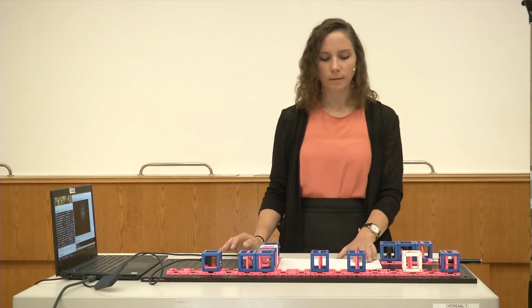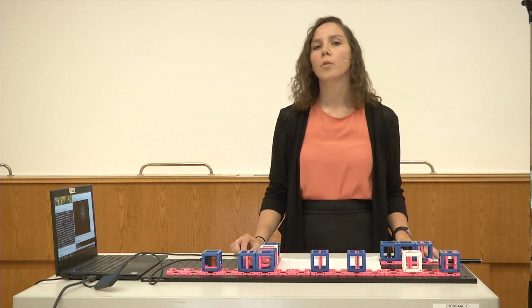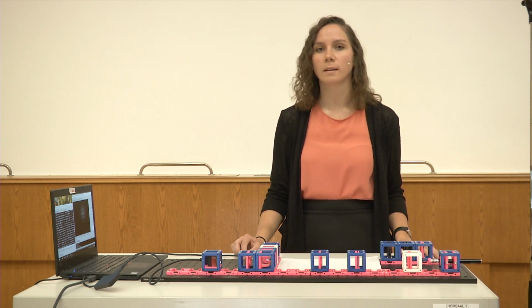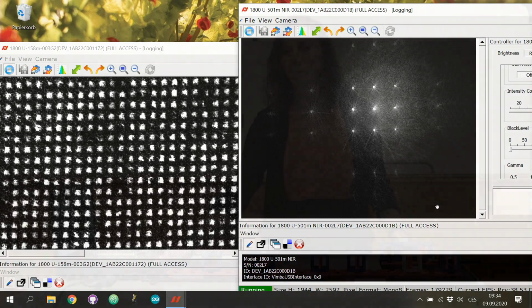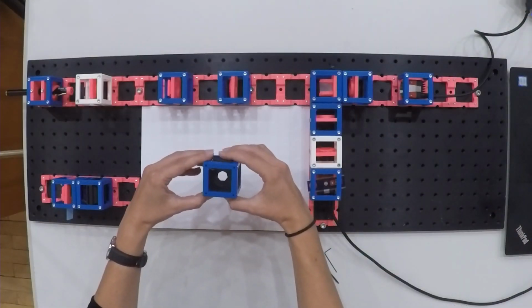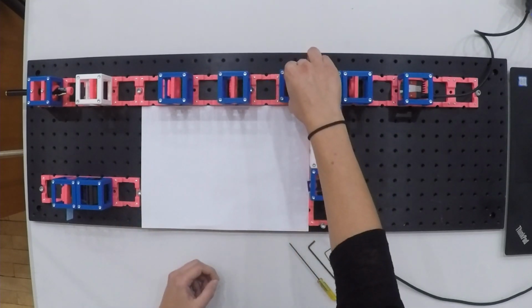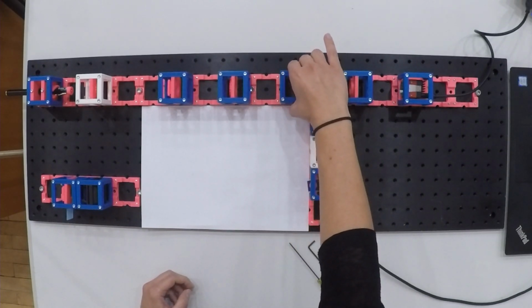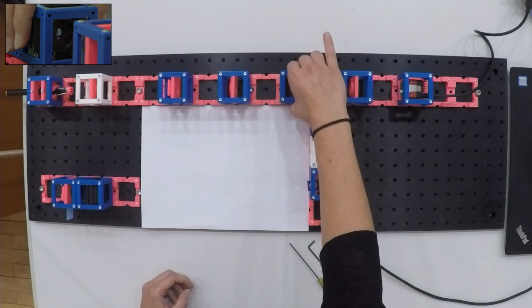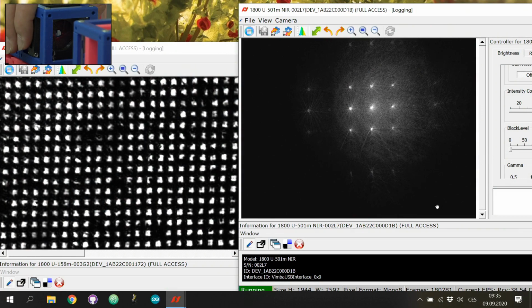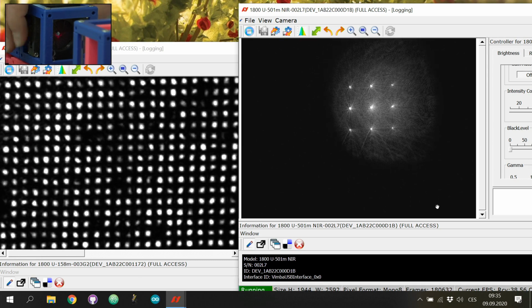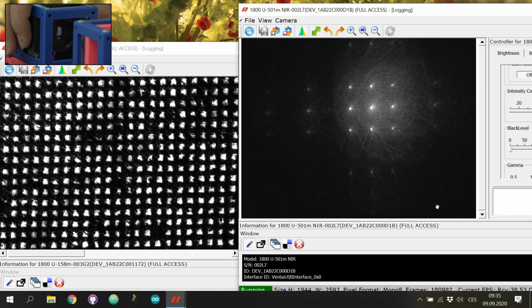I've mentioned that the image is formed by the rays diffracted by a detail, more precisely by the interference of the diffracted rays with the zeroth order, which is the central peak in our back focal plane, so this one here. Let's have a look at what this actually means. I'll start by placing a circular aperture in the back focal plane of the objective, here. And as I slowly close it, changing the diameter of the transmitting area, we block out the higher diffraction orders that form the image, and that carry the high frequencies and hence fine details. And we see in the image plane on the left-hand side that these details blur and the sharp edges soften. The more orders we cut out, the more blurry the image gets.